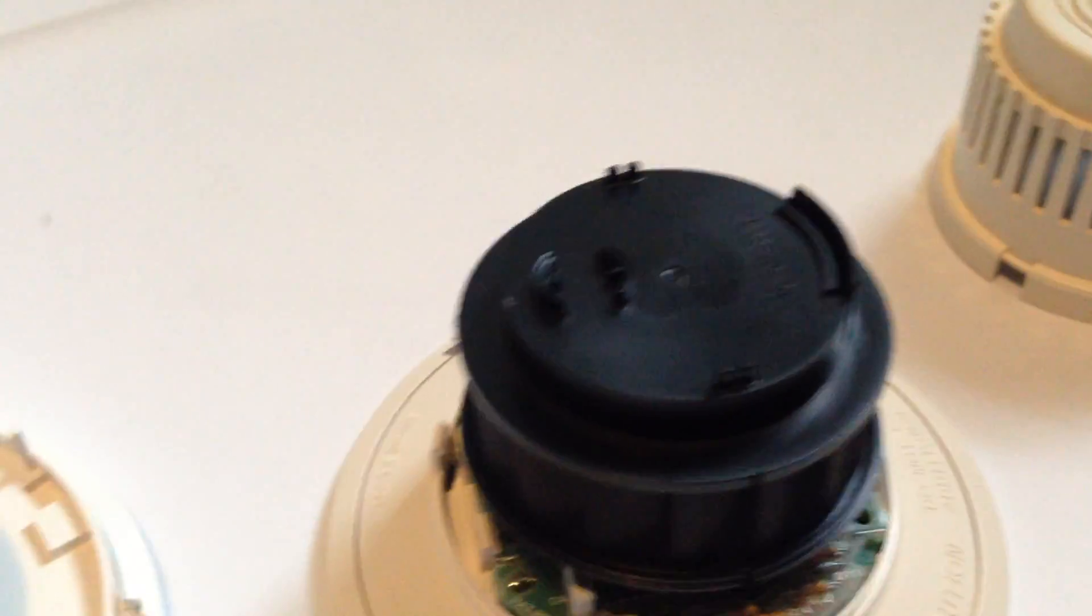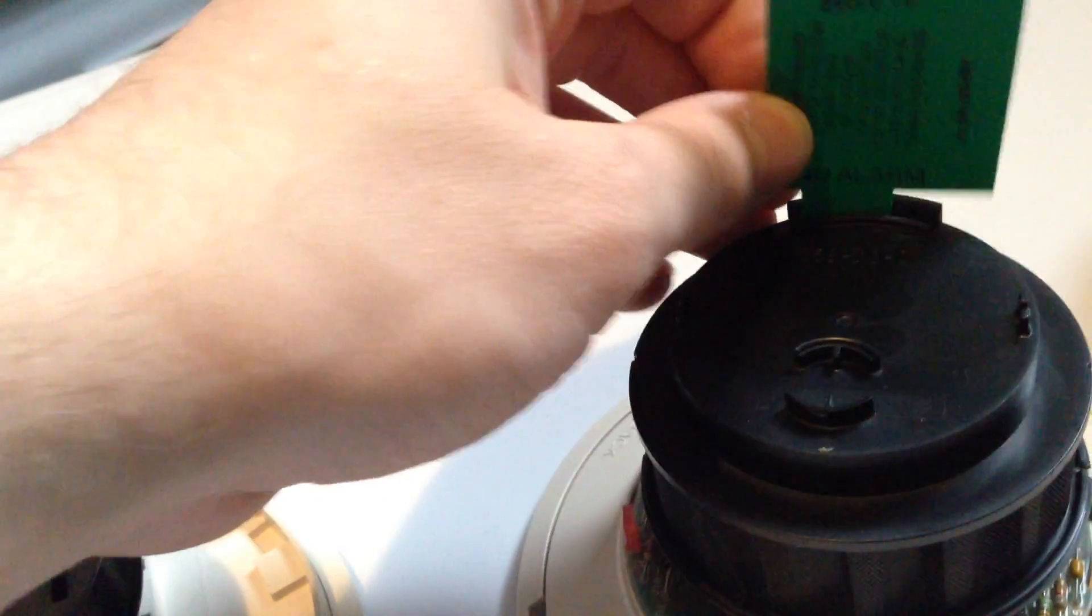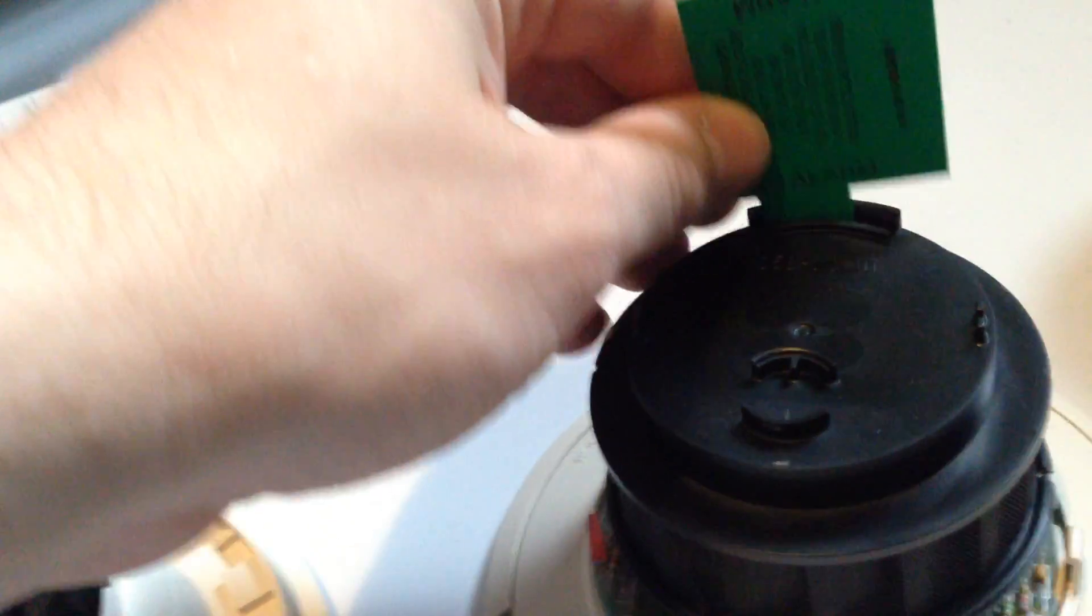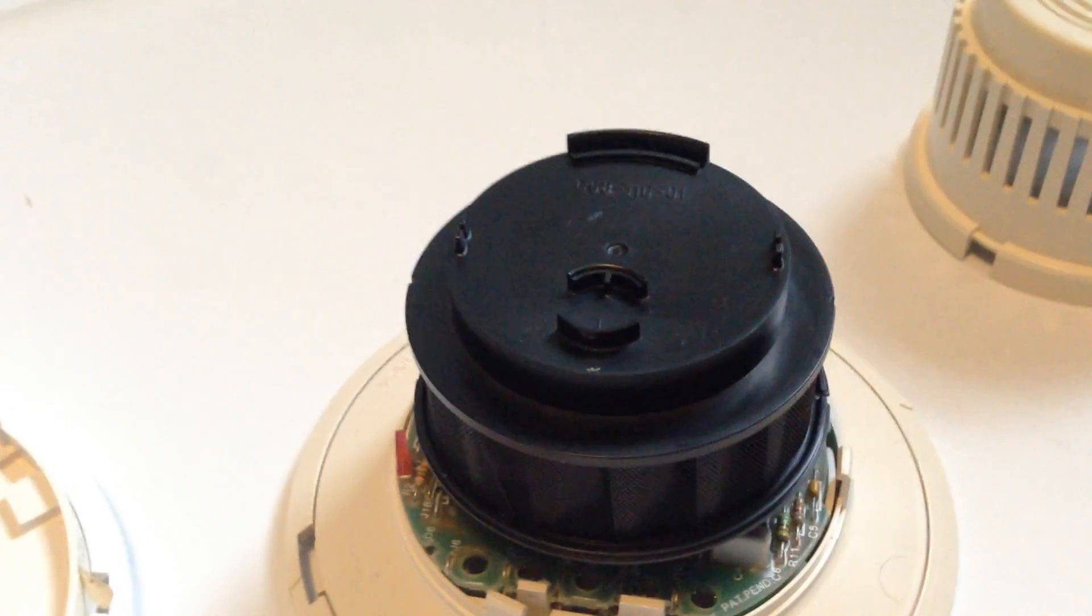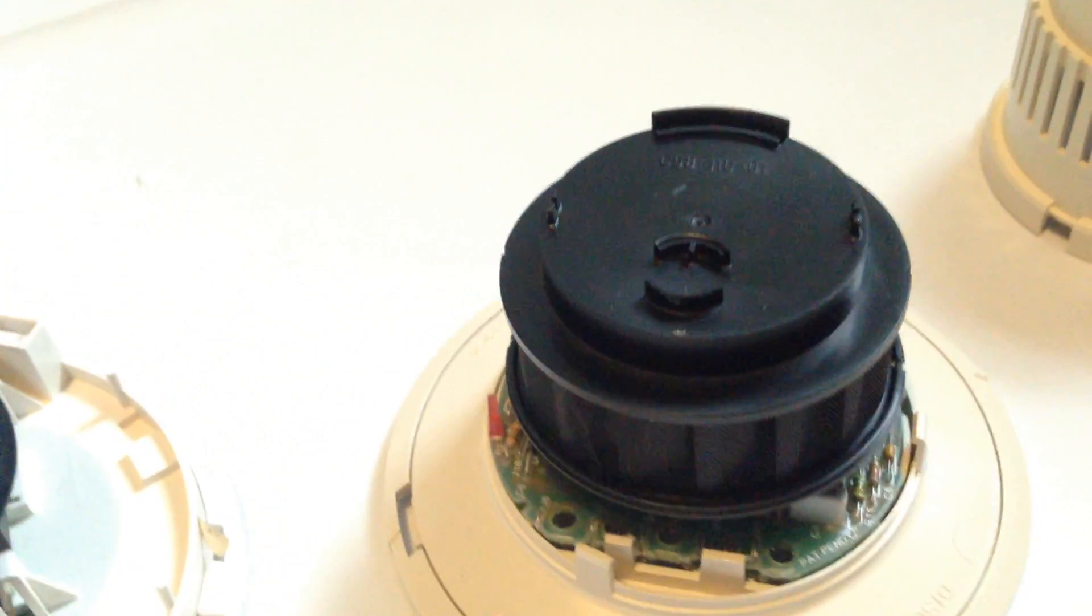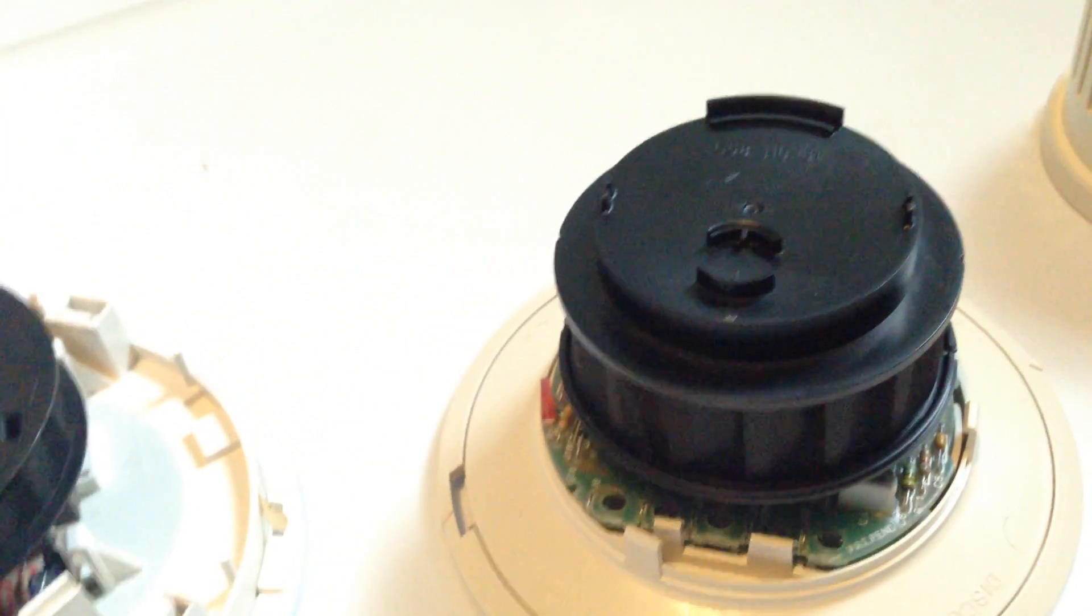Also, the way you test one of these 2800 detectors is there's a slot right here, and the cover actually has a slot on it, too. And there's a slot there, and you take this card. Now, for a sensitivity test, you insert the smaller end first, and then you slide it over, and that checks to see if the sensor is within its sensitivity range.